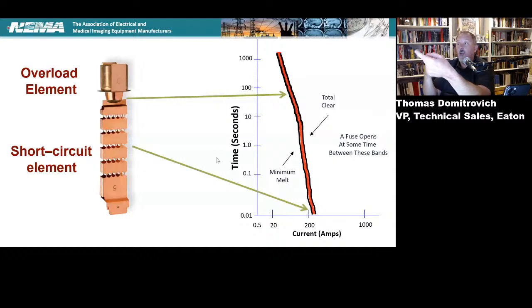But then you also have to think about coordinating with something upstream and downstream. And you want similar slopes throughout the power distribution system and not go crazy, because it could be hard to coordinate upstream and downstream overcurrent protective devices to ensure that downstream opens before the upstream does. So the way we construct these elements helps dictate the shape of that curve, and the current limitation capabilities, which is way over there to the right for very high fault currents. That little piece of physics that's sitting there on the left in that copper physics experiment is what gets you your current limitation and your overload and short circuit protection.